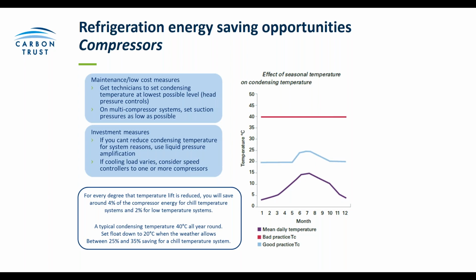Where you have multi-compressor systems, make sure the compressor suction pressure is set only as low as is required. So often the winter set point can be higher than in summer. In terms of investing in compressor systems, if you can't reduce the condensing temperature, liquid pressure amplification can be used, and so you can see savings of typically around 25% in this area, with paybacks of around 3 to 5 years. Where you have a varied cooling load across a wide range, consider using speed controllers for one or more of your compressors.